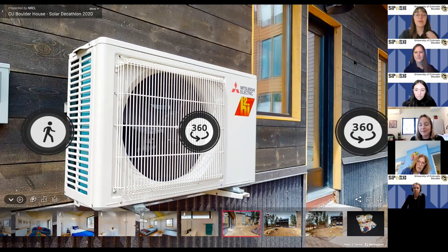Cold climate heat pumps are a newer technology that leverages inverter-based compressors and compressor cooling through the use of waste heat. And this provides about 1.5 to 5 times the heating capacity when compared to the amount of electricity needed, even in really cold temperatures.